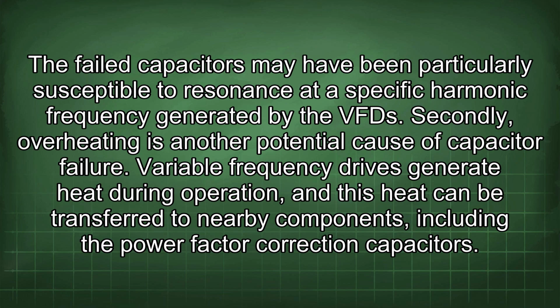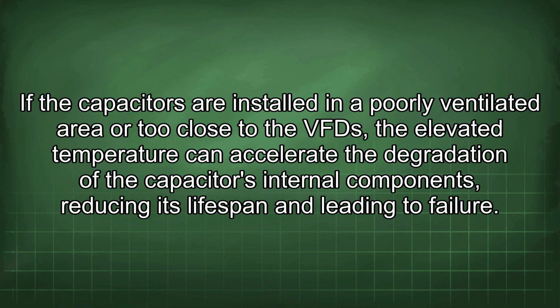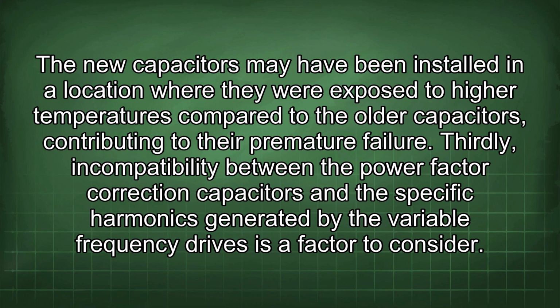Secondly, overheating is another potential cause of capacitor failure. Variable frequency drives generate heat during operation, and this heat can be transferred to nearby components, including the power factor correction capacitors. If the capacitors are installed in a poorly ventilated area or too close to the VFD, the elevated temperature can accelerate the degradation of the capacitor's internal components, reducing its lifespan and leading to failure. The new capacitors may have been installed in a location where they were exposed to high temperatures compared to the older capacitors, contributing to their premature failure.